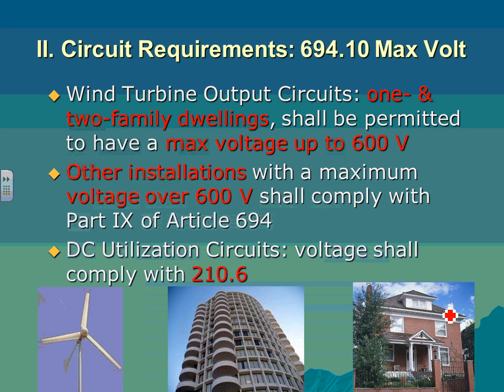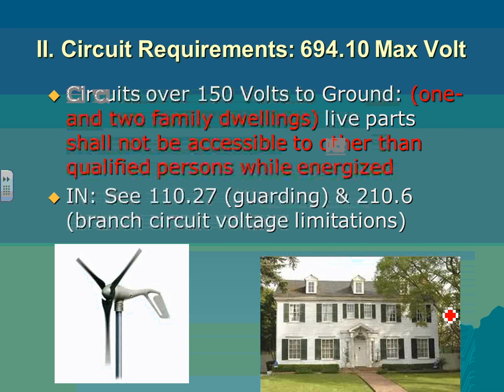If you don't care about the code from Nebraska, like he said, you can do anything you want, right? Now here's an interesting circuit, and they give you the maximum voltage. Circuit over 150 to ground. If you're up to 150, that gives you 120 to ground and 240, typical for dwelling, right? 120/240.